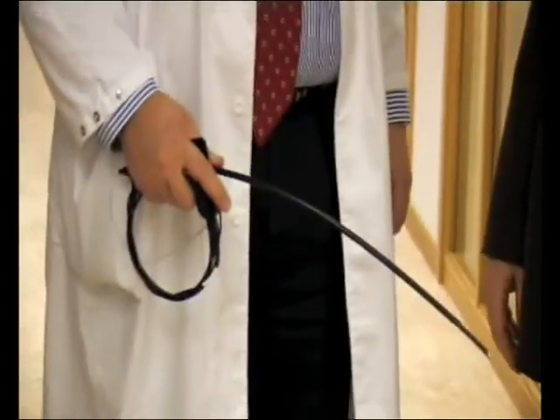ICD and pacemaker systems consist of leads and devices. The leads are transvenously implanted into the heart. Over time, these leads undergo fibrotic encapsulation, and it's not possible to simply pull them out. So if you have an infection of the device system, or you need to take out leads that are non-functional or superfluous, you need to use special methods.